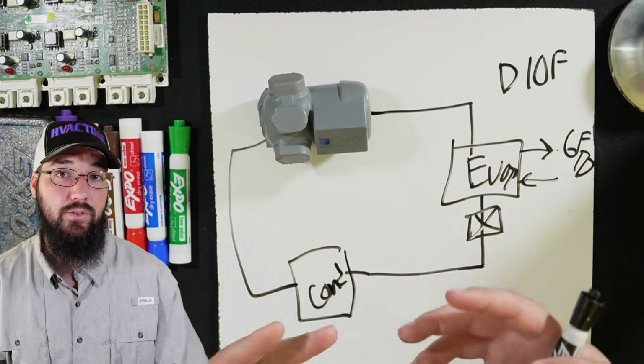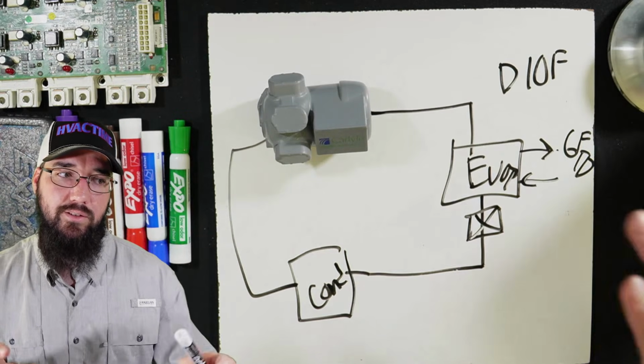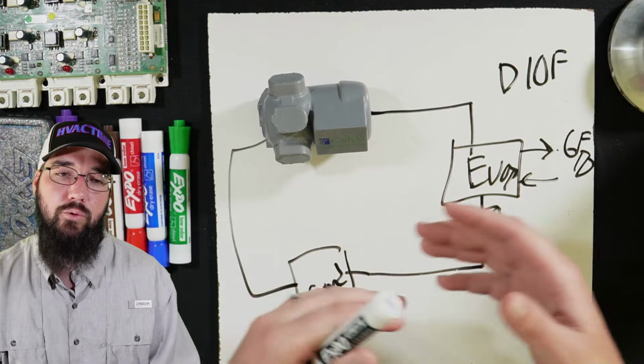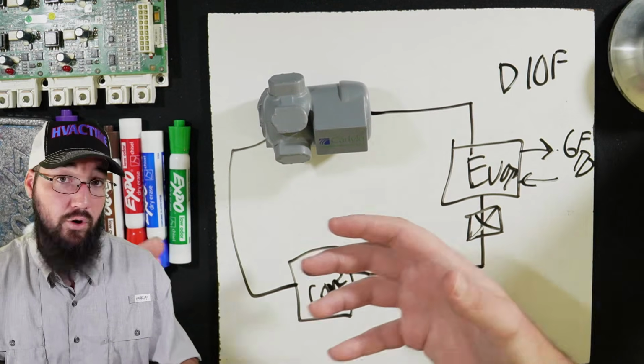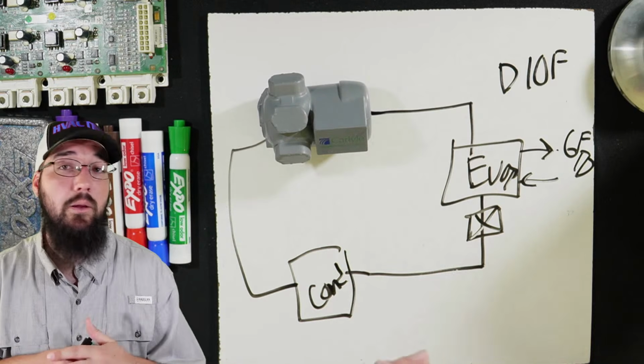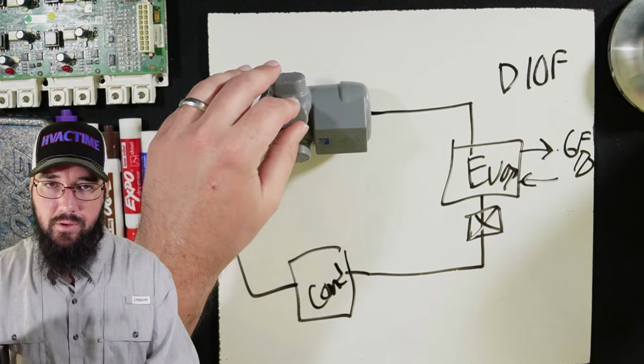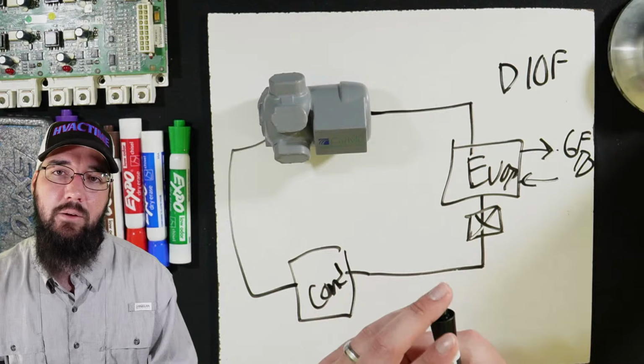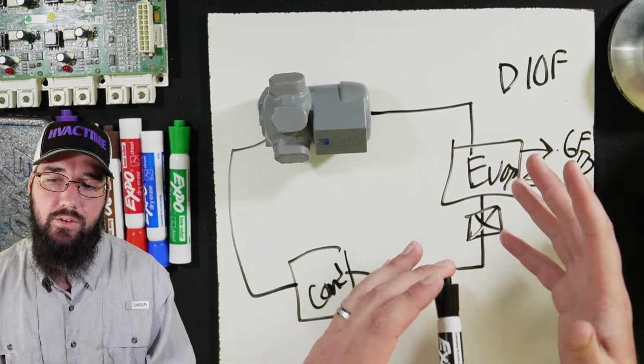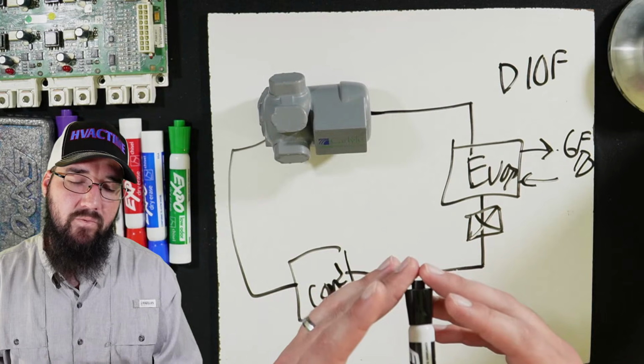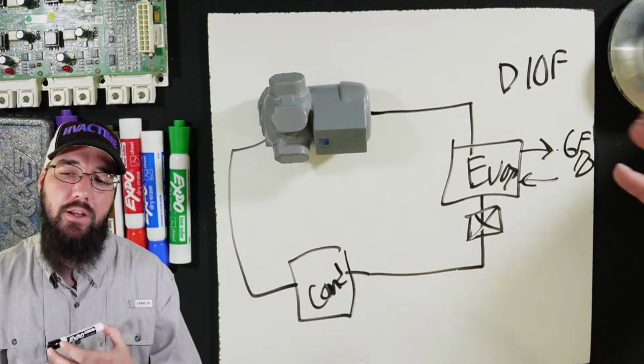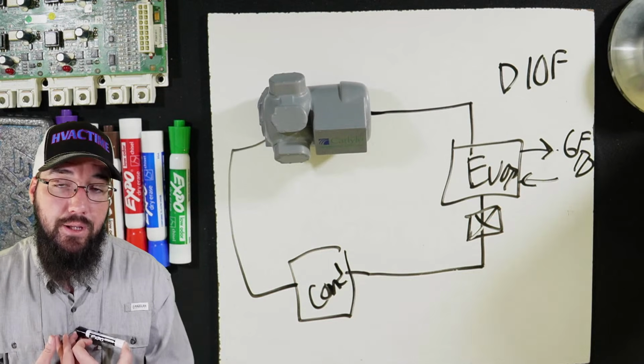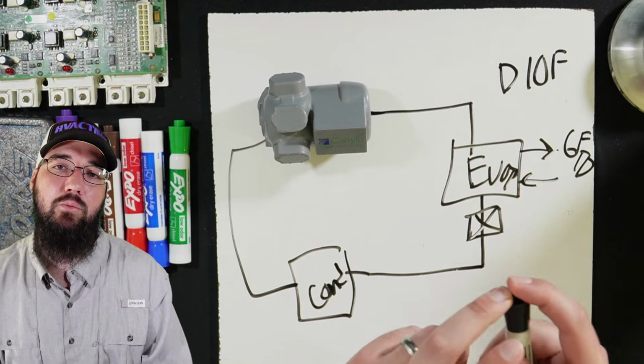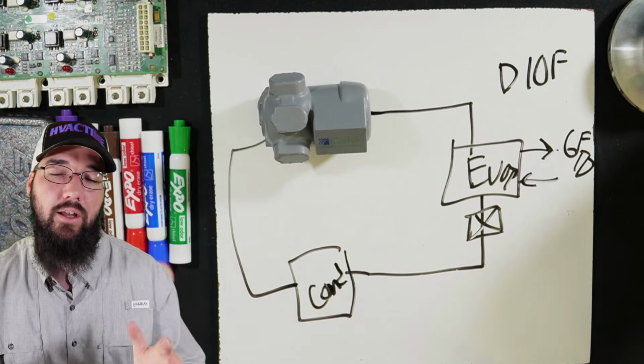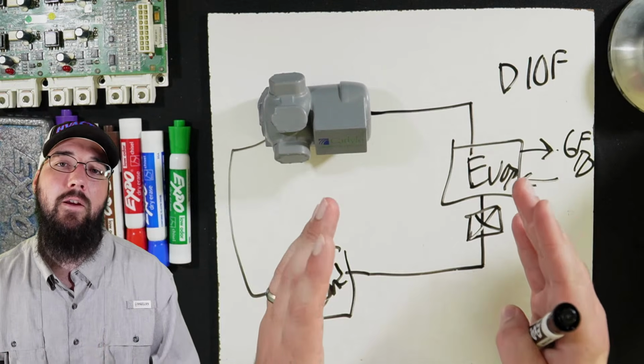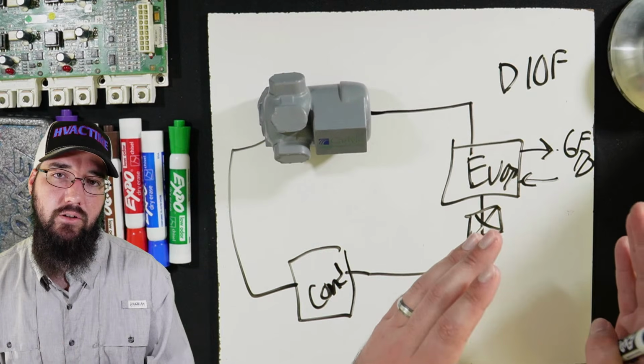So if we're doing more of a comparison, comparing versions, like from a recip to a scroll to a screw, you're going to get better efficiency out of a screw in part load conditions. By far, in my opinion. Maybe the inverter screws with permanent magnet motors kind of challenge that, but the point is, it's not just because of approach lowering and the heat exchange, like what we're discussing, that is not the core driver, in my opinion, as to why a screw is more efficient. It has more to do with managing the load on the compressor, not necessarily the heat exchanger. And with approach specifically, we're focused on the heat exchanger, not necessarily the compressor.